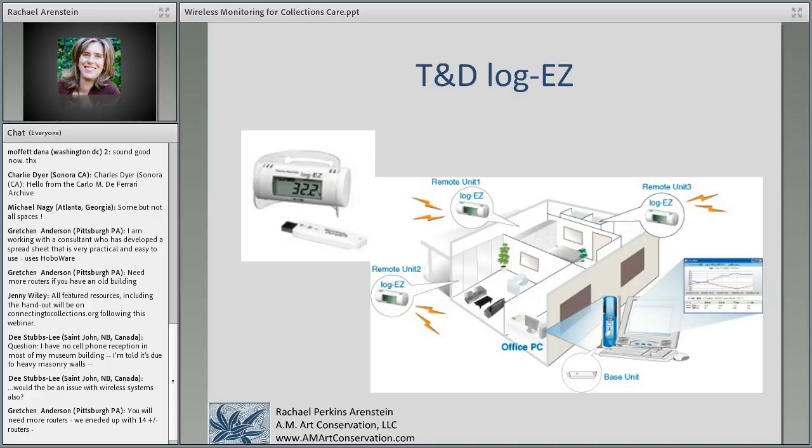The thing that looks like a little flash drive is called a wireless dongle. That needs to be inserted into your PC or laptop into the USB port, and it remains there. And so basically, your loggers are going to be transmitting back to that wireless dongle. They have a 50 meter line of sight transmission range. So the line of sight here is even less than what is on a system like the Hobo nodes.